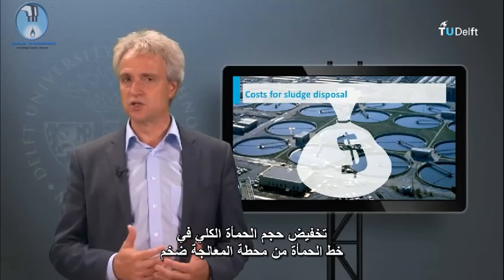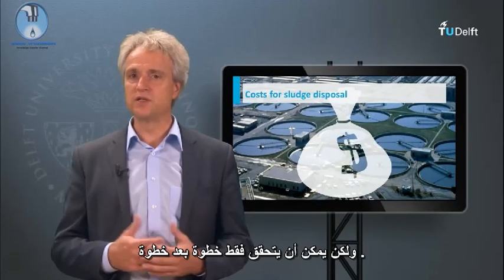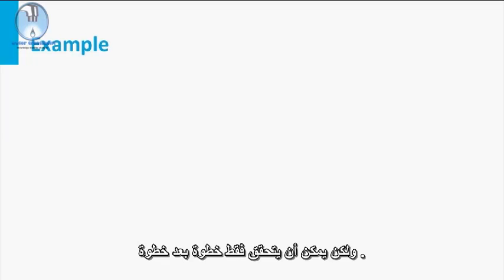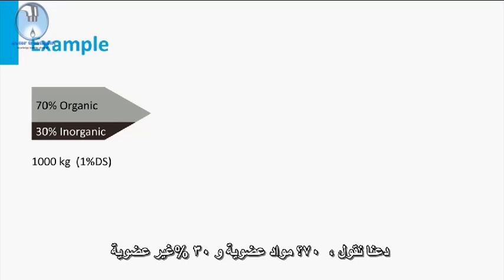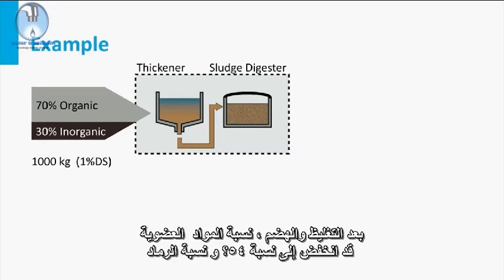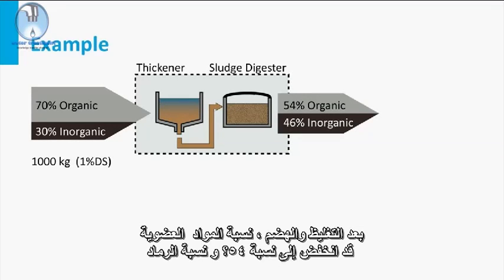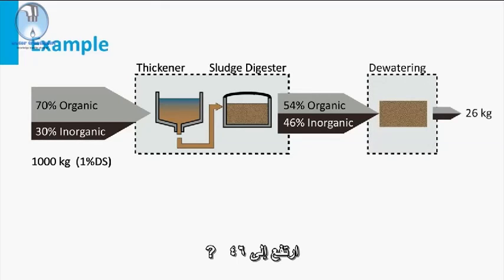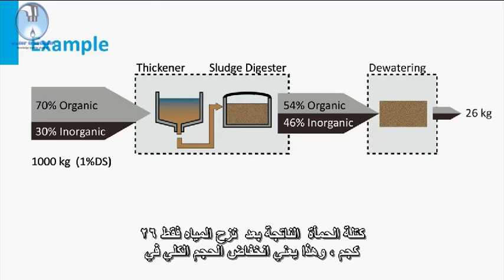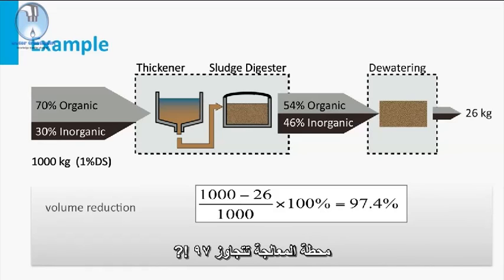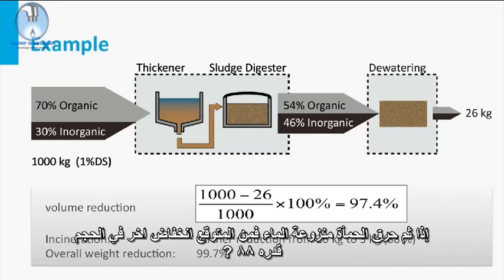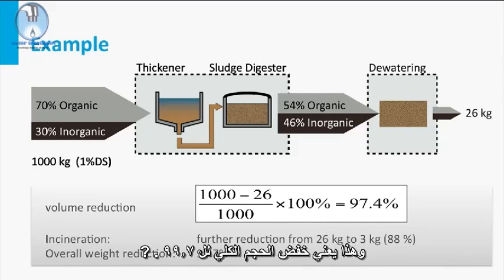The overall sludge volume reduction in the sludge line of the treatment plant is huge, but can only be achieved step by step. For example, at the start, a sludge stream of 1,000 kg has 1% dry solids, of which 70% is organic and 30% is inorganic. After thickening and digestion, the organic fraction has dropped to 54% and the ash fraction has increased to 46%. Dewatering results in a sludge mass of only 26 kg, meaning a total volume reduction at the treatment plant exceeding 97%. If the dewatered sludge is then incinerated, a further volume reduction of 88% is expected, meaning a total volume reduction of 99.7%.